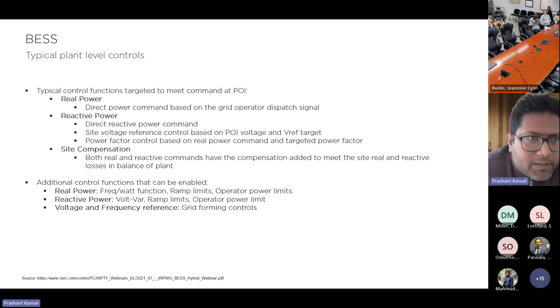And then there is this whole new world of grid forming controls, which in simple terms is nothing but a synchronous machine with current limits on it. Because inverters can only do so much current — they are not a mechanical device, they're electronics devices. Switches have their own limitations, MOSFETs have their own limitations. So you have to have some kind of current limits on those devices. That is really part of the core control here.